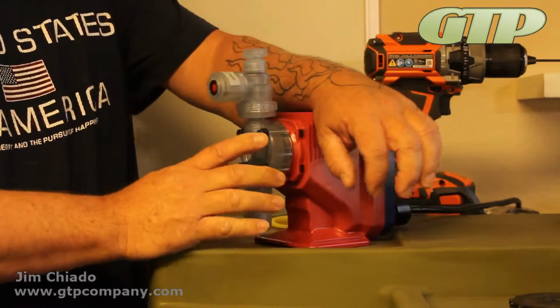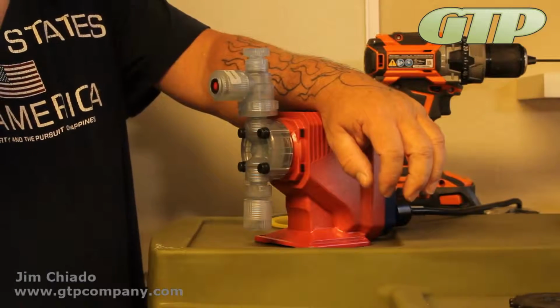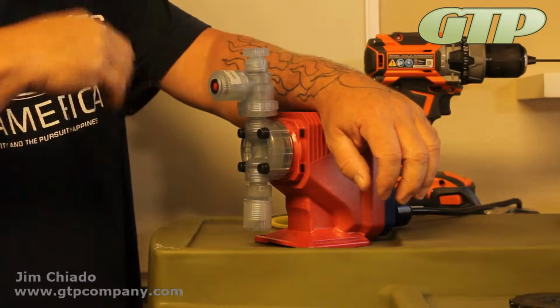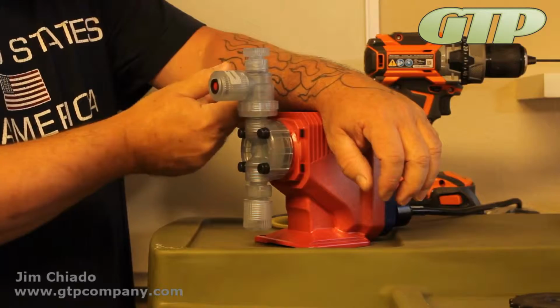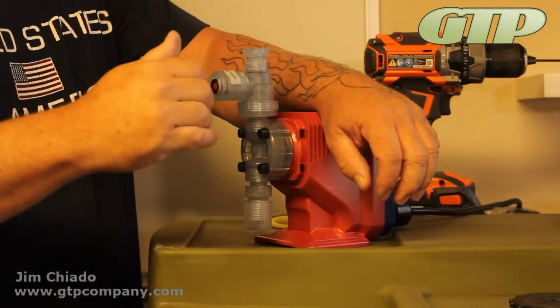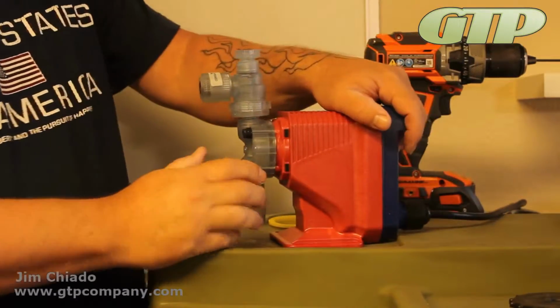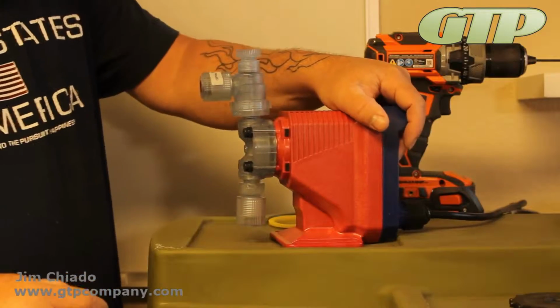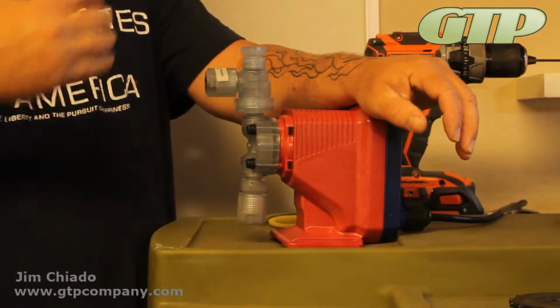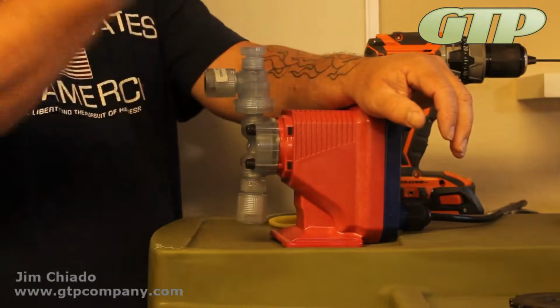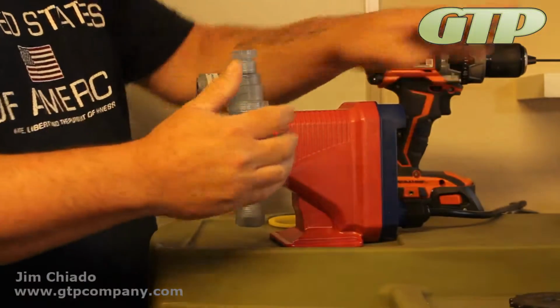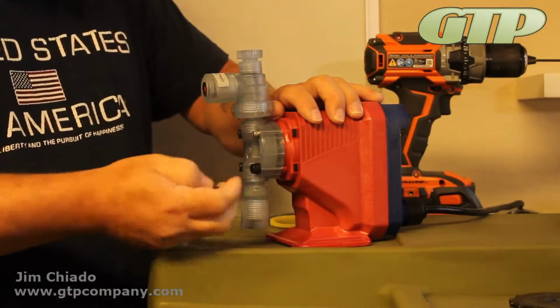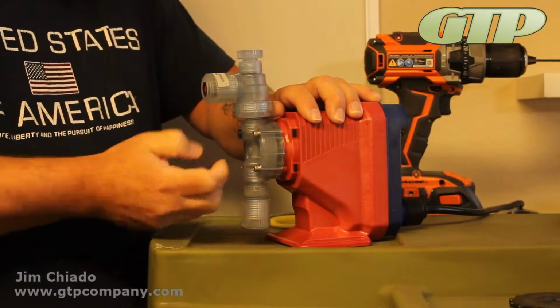The first thing I like to do, especially when I get a pump in for repair, I always make sure that it's cleared out. The reason being, when you plug a pump in, if it's left in the on position, it comes right on and starts pulsing, and you don't want to have chemicals in there when the repair technician does it. I never plug a pump in first. The first thing I always do is remove all the things, remove the pump head.